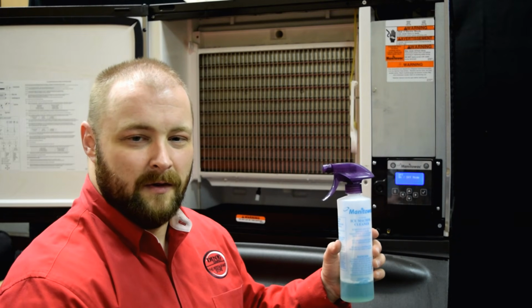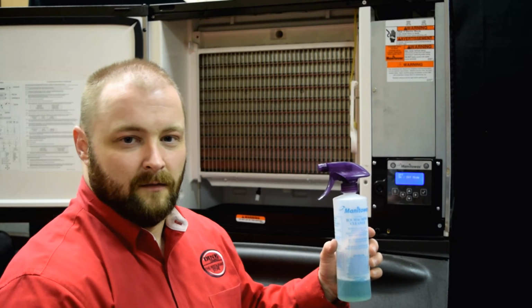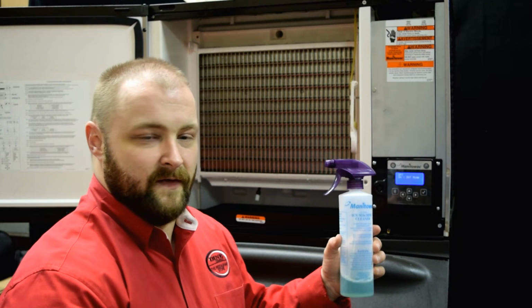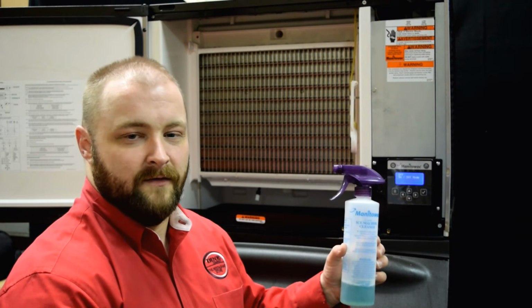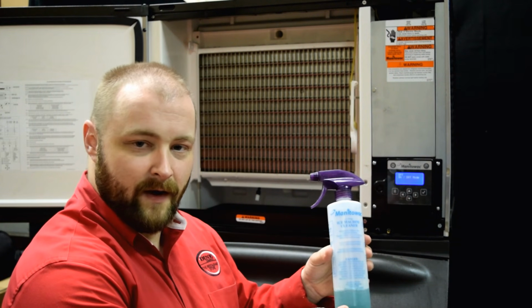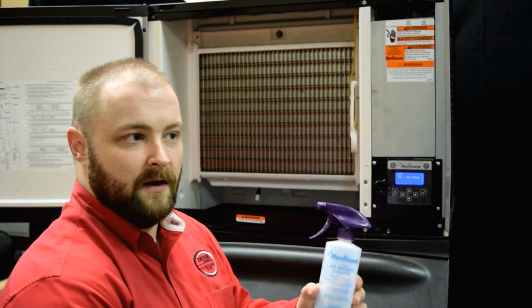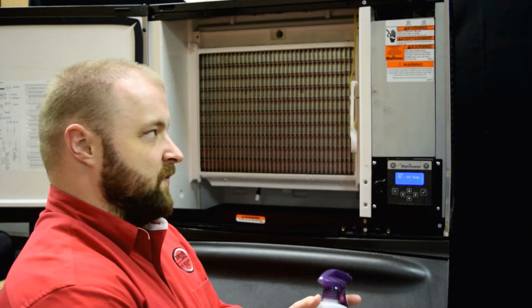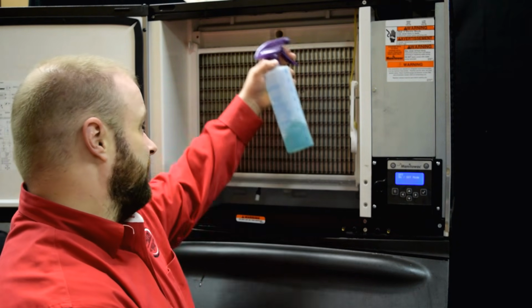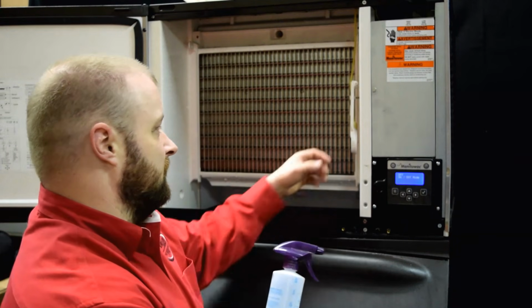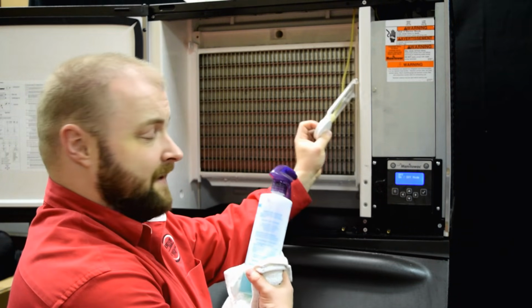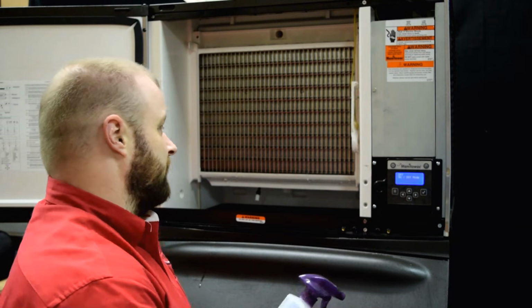Now that the main components are removed, we can go ahead and clean any surfaces inside the ice machine using a dilution of Manitowoc Ice Machine Cleaner and water and a soft cloth. You simply apply the cleaner on the outside surfaces, including the ice thickness probe, which we left hanging, and then clean the machine.